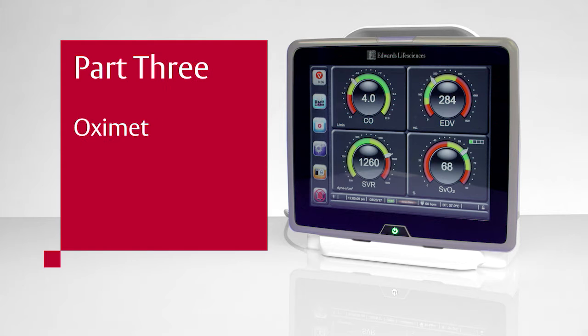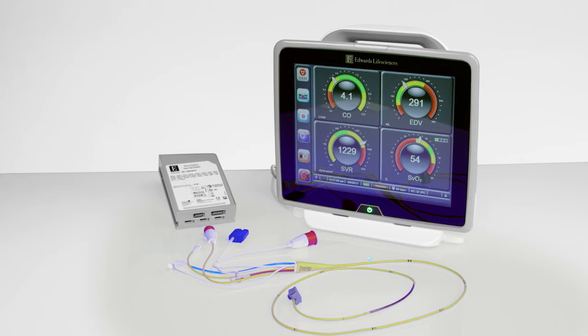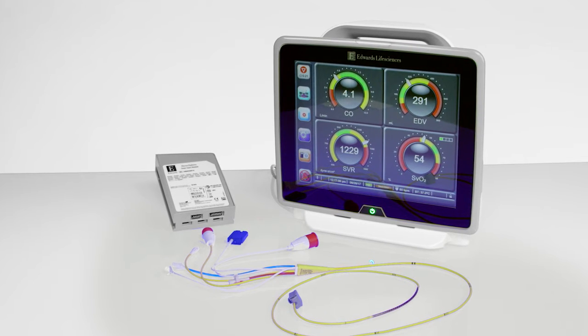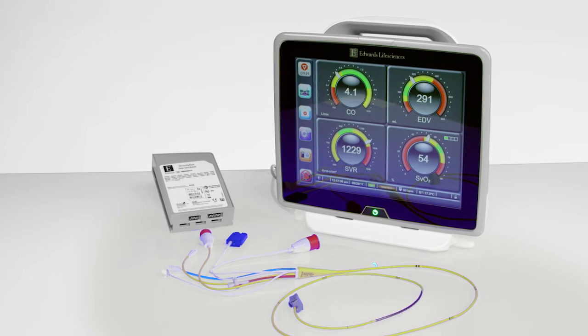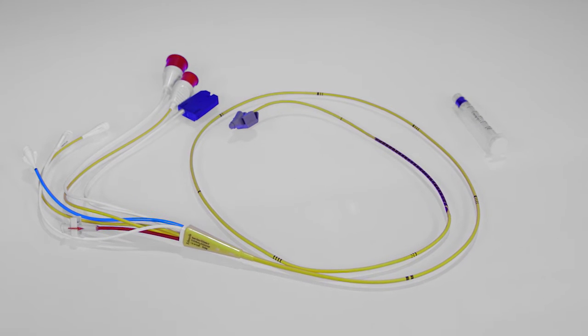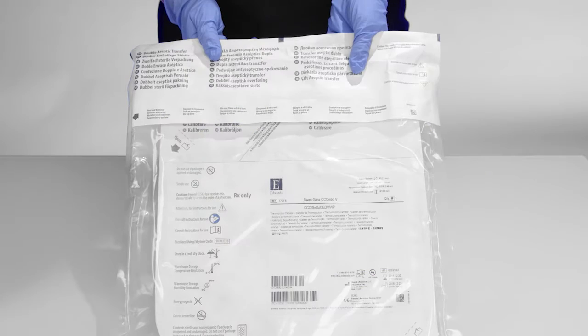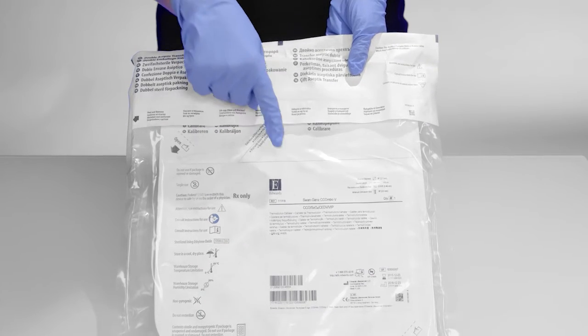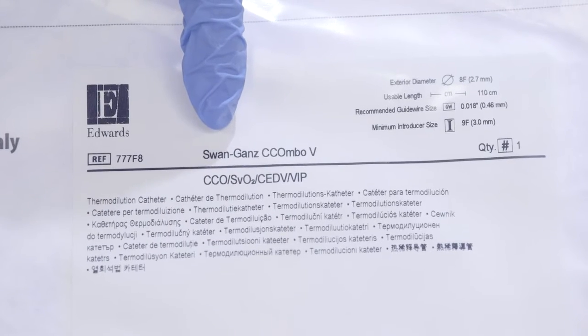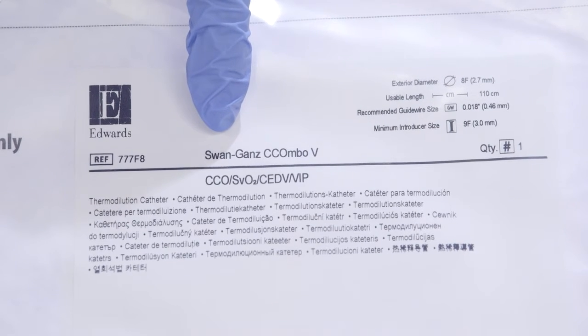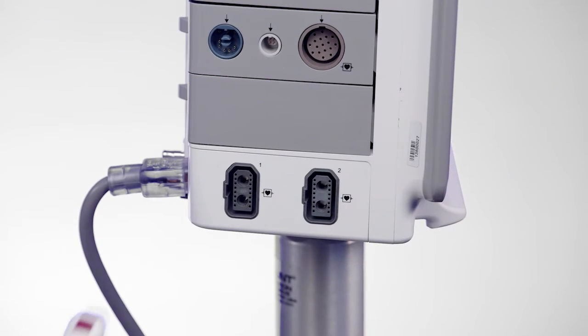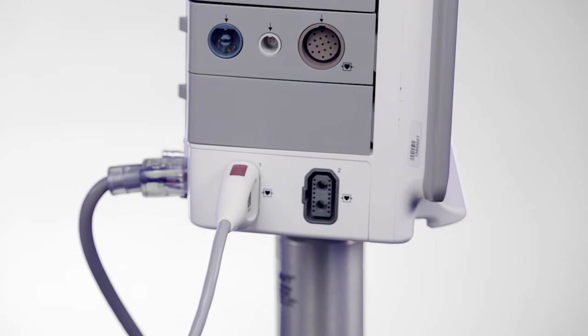Part 3. Oximetry Setup. To utilize the HemoSphere Advanced Monitor's SVO2 monitoring function, you must use a Swan-Ganz catheter that has SVO2 capability. Your first step is to check the catheter packaging to confirm you're using the intended Swan-Ganz catheter. To monitor SVO2 with the Swan-Ganz pulmonary artery catheter, plug the HemoSphere oximetry cable into one of the ports at the bottom of the HemoSphere Advanced Monitor.